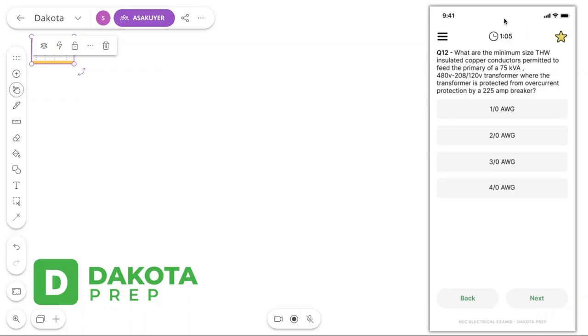Okay, so the good news is, pretty easy question here, okay? And it's pretty easy because of 240.4. 240.4 says, hey, conductors shall be protected against overcurrent protection in accordance with their ampacities, right? So that means that the ampacity of our conductor has to be protected, right? Now there are a couple of other rules in there. In fact, right there in 240.4, 240.4(B) says, well, if your conductor ampacity doesn't correlate with the standard size overcurrent protective device, you can go up to the next overcurrent protective device in general, but there's some situations where you can't. Okay, for this one though, pretty straightforward.